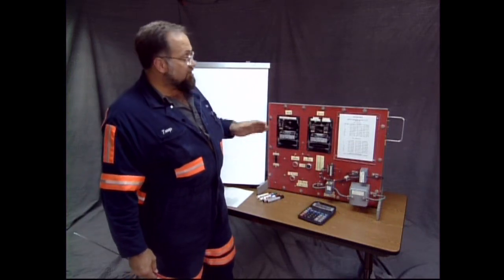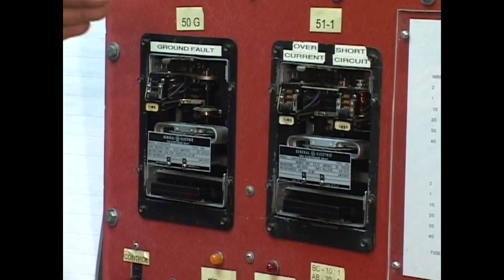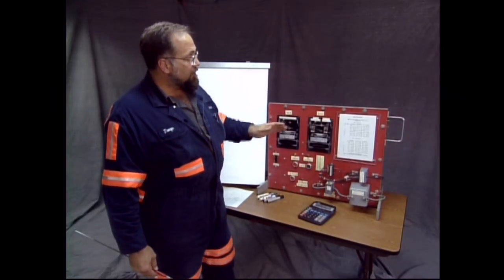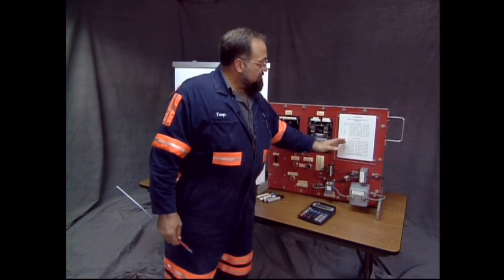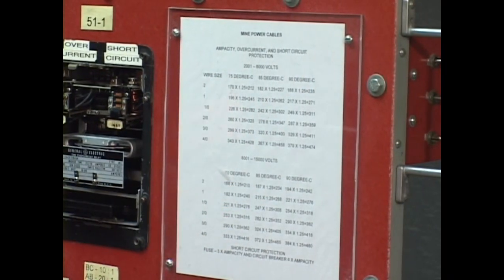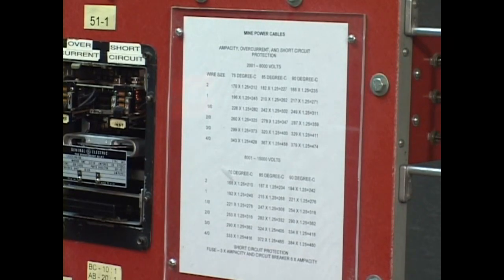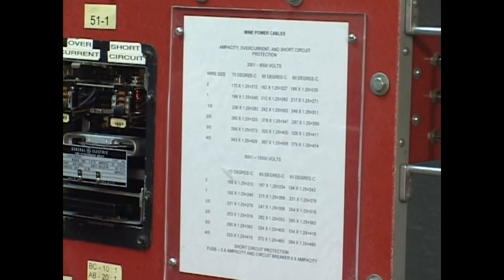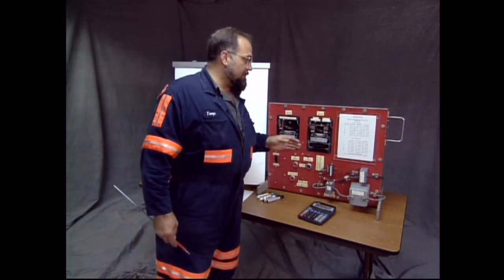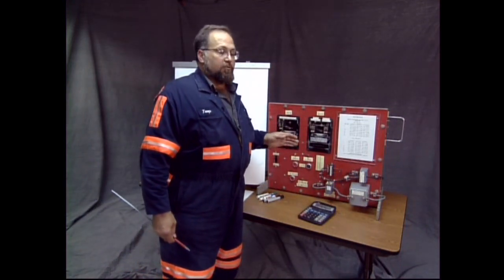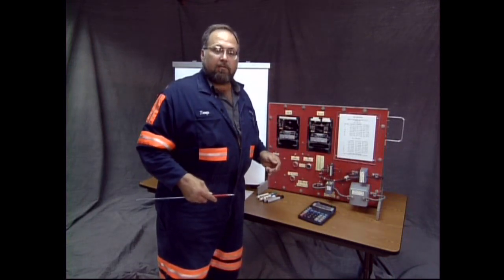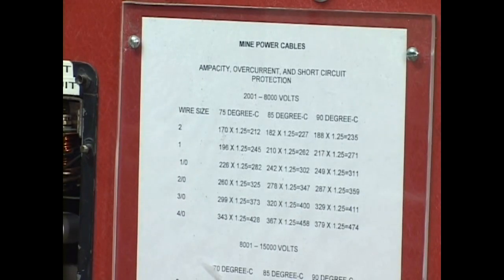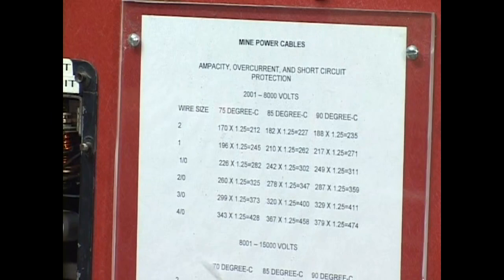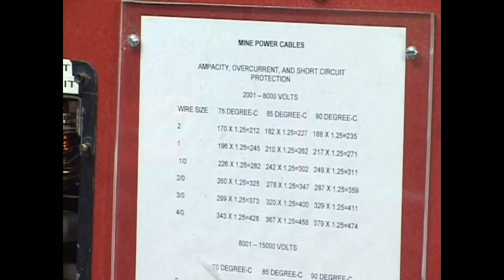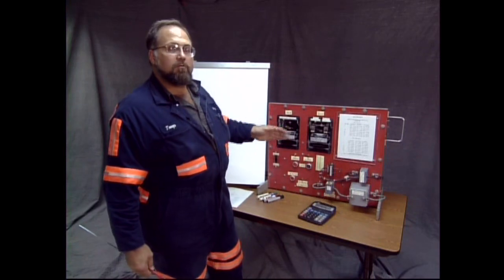Another part of the visual exam is the setting. These breakers are wonderfully adjustable. The breaker relay panel is wonderfully adjustable. You see all these cable sizes here and all these different thermal ranges of the cables. You can adjust this device to fit any of those cables. But now, all those settings aren't correct. You're going to make a visual examination. You're going to check what size cable you have, and then set within those parameters, not to exceed the approved settings for that particular size, insulation, and thermal value of the cable. All right, thermal rating of it. So that's all part of your visual and manual operation.